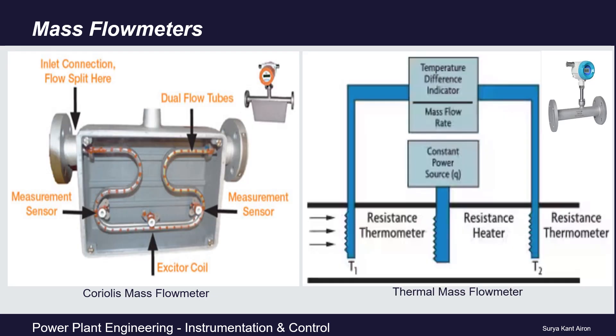All the flow meters discussed so far — velocity type, variable area, and differential pressure — measure volumetric flow. Volumetric flow rate varies with temperature and pressure, so additional temperature and pressure compensation is required. Another important type are mass flow meters, which measure direct mass flow independent of temperature and pressure variations. Examples include Coriolis mass flow meters and thermal mass flow meters.